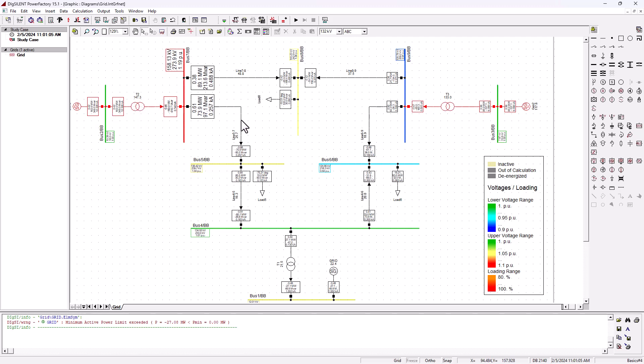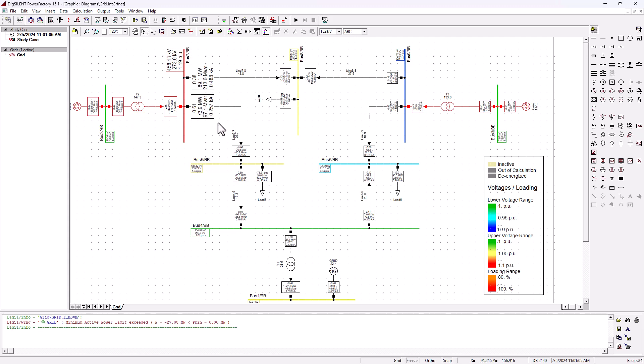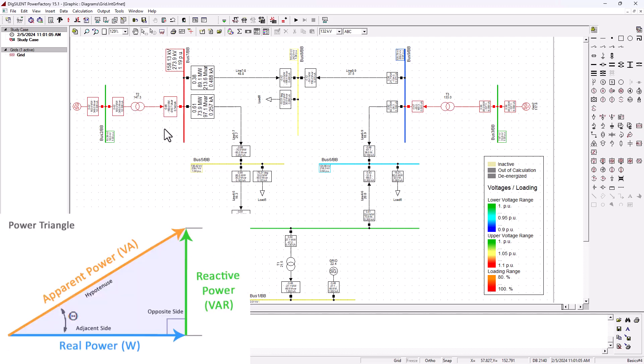You're causing this generator to overwork and that is causing this transformer to basically be overloaded. Because of all this instability, now we're causing this transformer to be overloaded and we've got 163 megawatt of real power that's being drawn and 348 that is being basically generated to compensate the system instability. Now the transformer is overloaded.